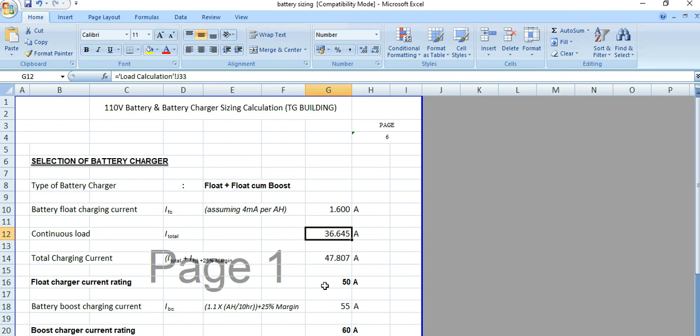Then the total charging current is the sum of these two values multiplied by a 25% margin. So IFC plus I total multiplied by 1.25.